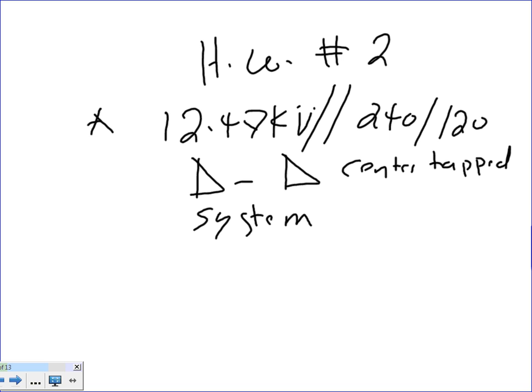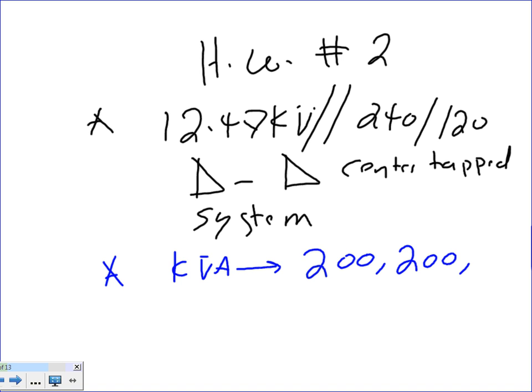Now the sizes that I'm going to use for each transformer, so that's what we get. The sizes for each one, let's go by size. Okay, so sizes are in KVA. I'm going to go by 200, 200, and 300. Everybody knows what the 300 would be? The 300 would be the fat one that's sitting for the neutral, giving the neutral. They always give you two the same, one different.